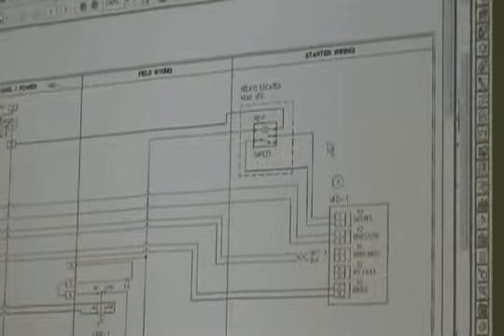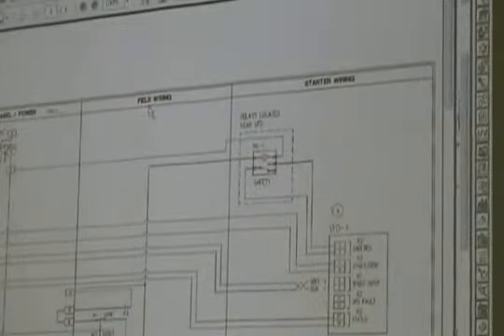Then the next section is showing the actual field wiring that goes between a panel and out to the air handler. And then this last section is showing the starter, or in this case, the VFD. That relay, by virtue of being under this category, tells me that that relay is mounted in the VFD, or in this case, located near the VFD. So that gives us 4 different sections to tell the guys that this should be mounted here, this should be mounted there. If you notice, all your temp sensors, low temp detector, those kinds of things are showing out here in the field, which is part of the air handler.